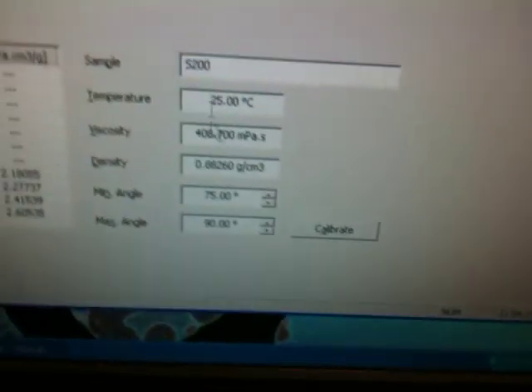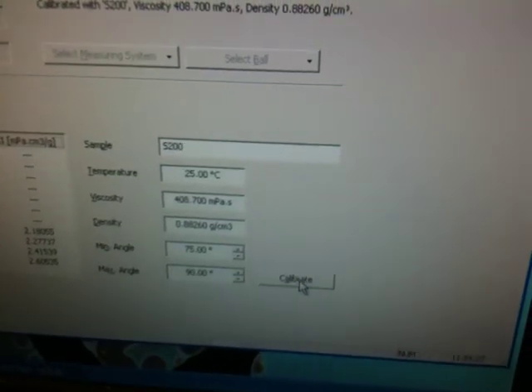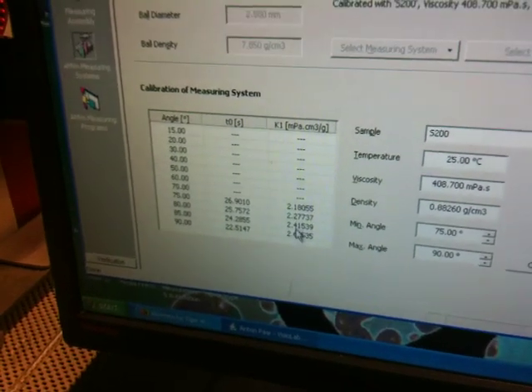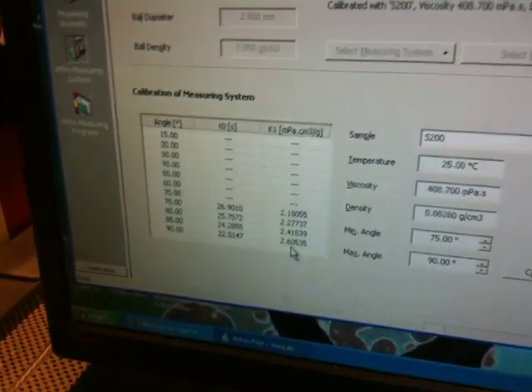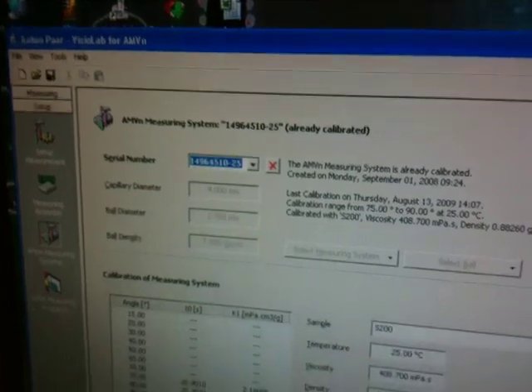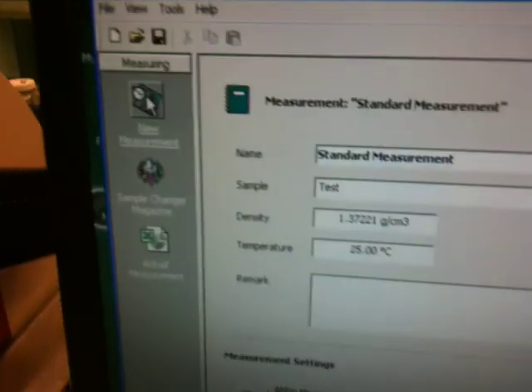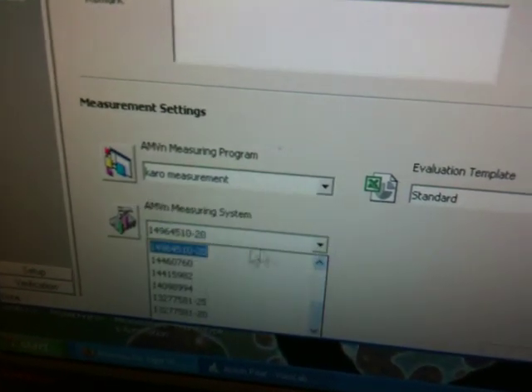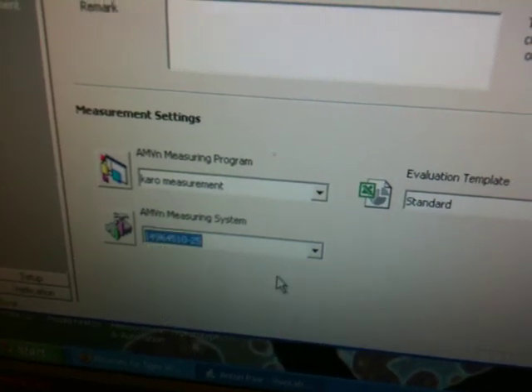And then once you've put your sample in, fixed all this information the way you want it and the name, all you have to do is hit calibrate. And then it will come out and give you the K1 constants that it uses, so that now you remember this name, you come back to the measuring, and when you're doing a new measurement, you come down and make sure that your measuring system is the same. That's all you have to do to calibrate it.